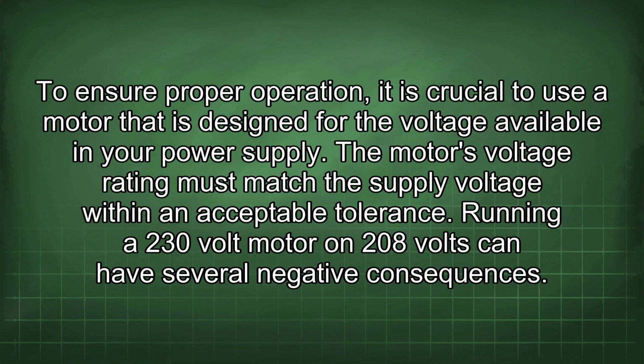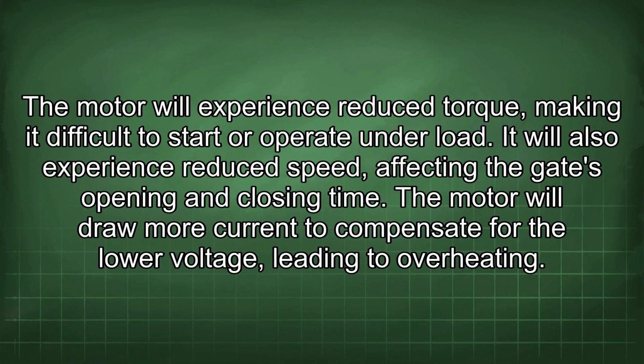To ensure proper operation, it is crucial to use a motor that is designed for the voltage available in your power supply. The motor's voltage rating must match the supply voltage within an acceptable tolerance. Running a 230-volt motor on 208 volts can have several negative consequences. The motor will experience reduced torque, making it difficult to start or operate under load. It will also experience reduced speed, affecting the gate's opening and closing time.